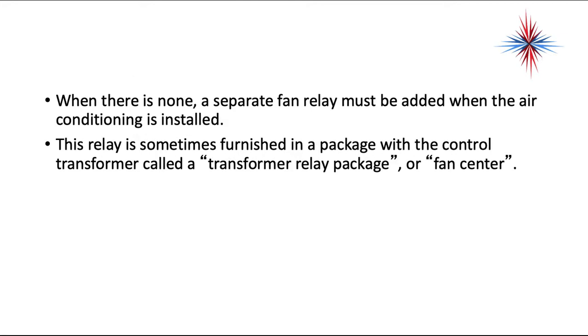So when there is no separate relay, a fan relay must be added when the air conditioning is installed. The relay is sometimes furnished in a package with the control transformer called a transformer relay package or a fan center.